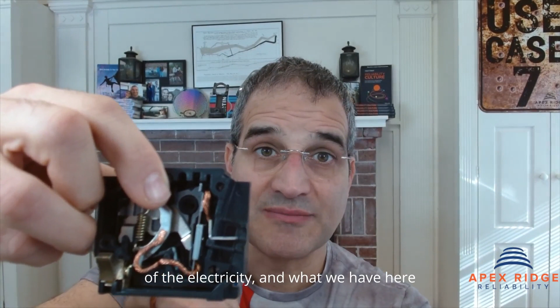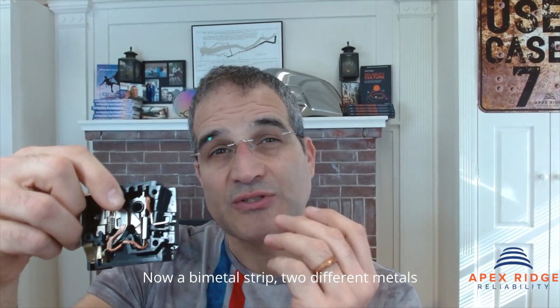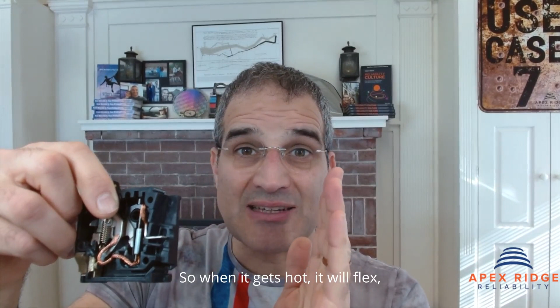And what we have here is a bimetal strip, two different metals with two different thermal expansion coefficients. So when it gets hot, it will flex and move while it's carrying amperage through it. When the amperage gets high enough, it works as a resistor, gets enough heat, and it will actuate - let's see if I can do it backwards - so when it moves a little bit, it'll actuate and open the circuit.